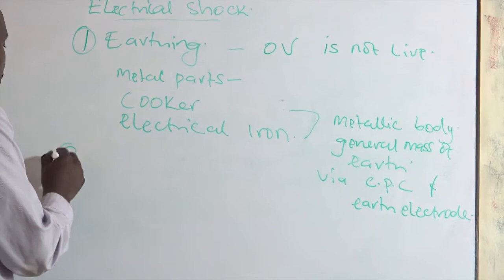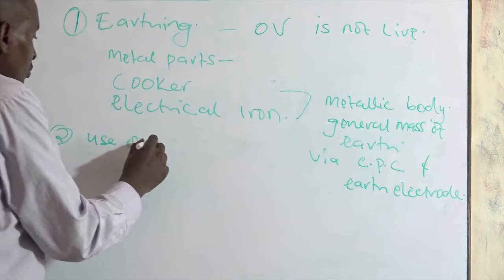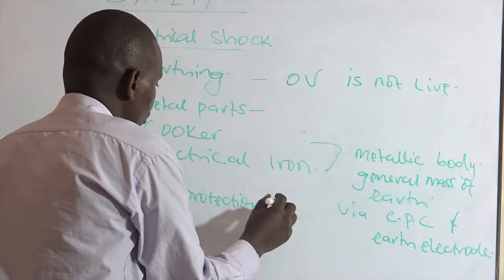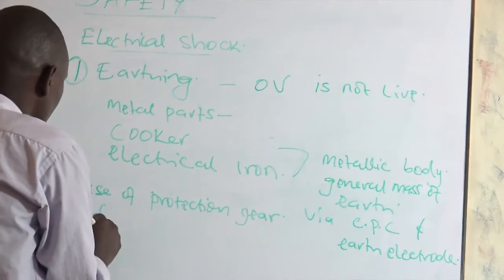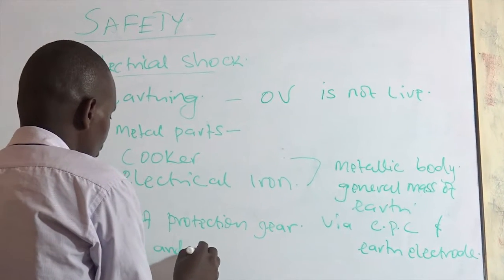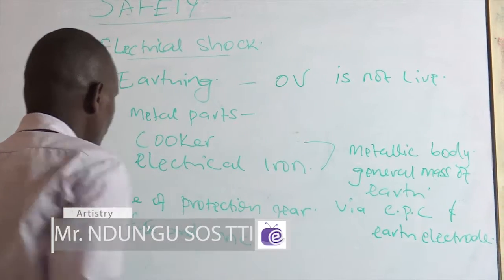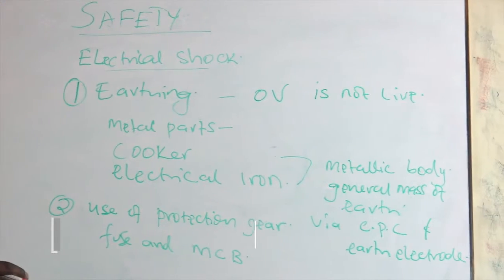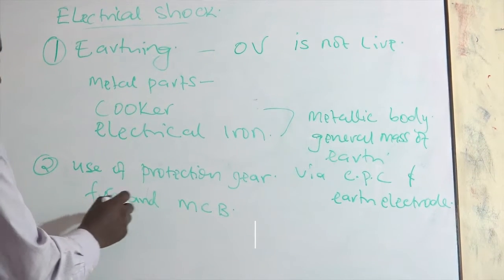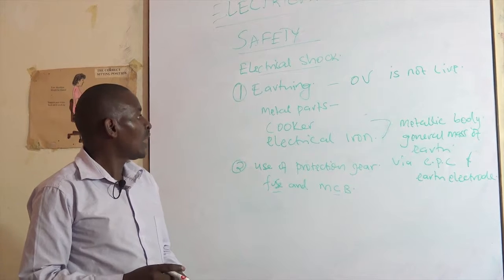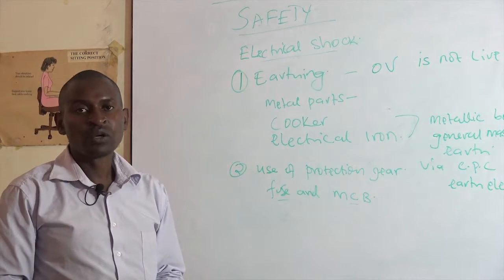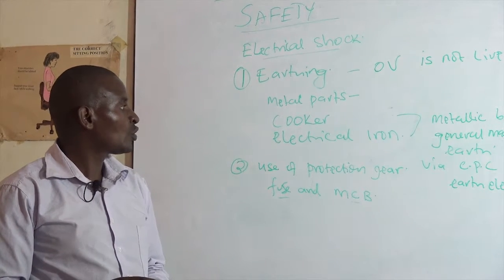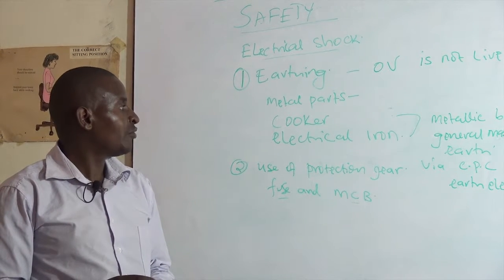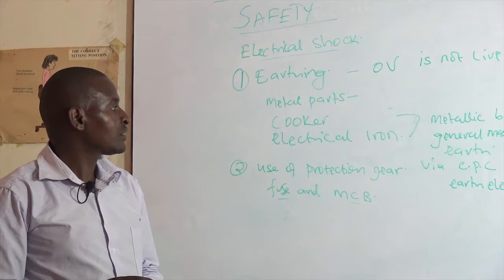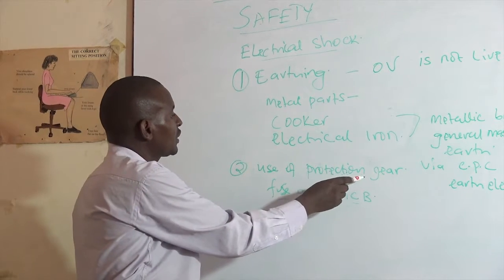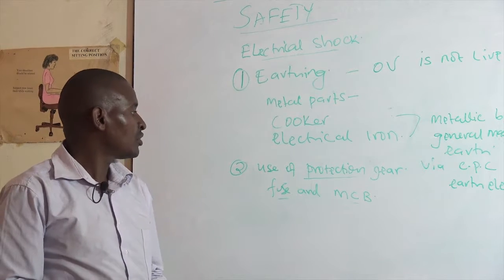The other thing that is done, number two, is the use of protection gear, and here we use fuses and MCBs. This is what happens when you have an electric fault whereby the live conductor is in contact with the metallic part of the equipment. What should happen is that there should be a very low resistance path to pass this current. And once the current is passed, the protection equipment, that is either the fuse or the MCB, should operate.